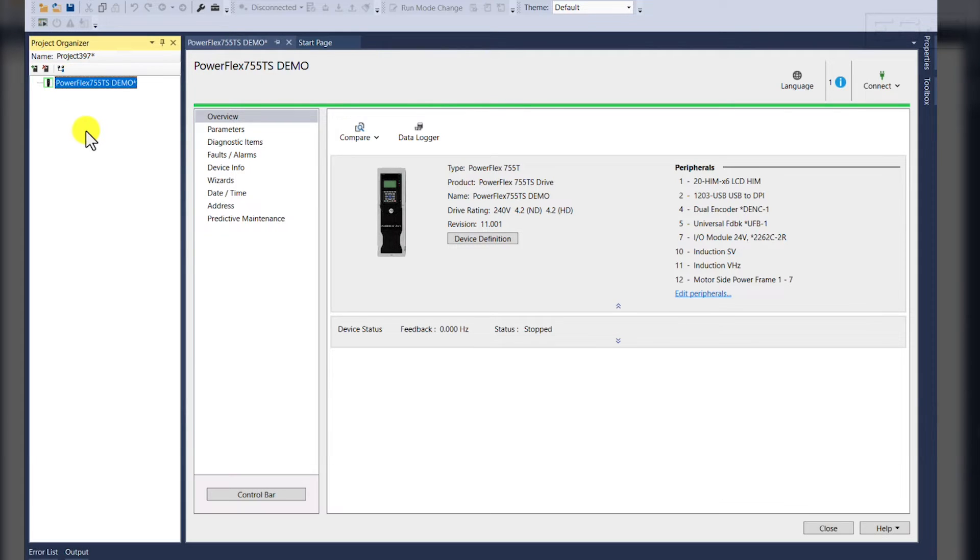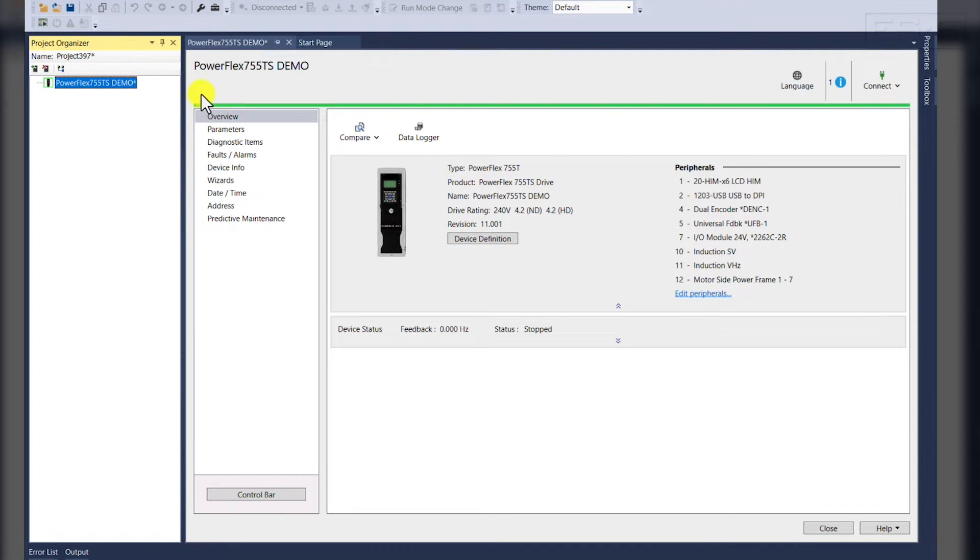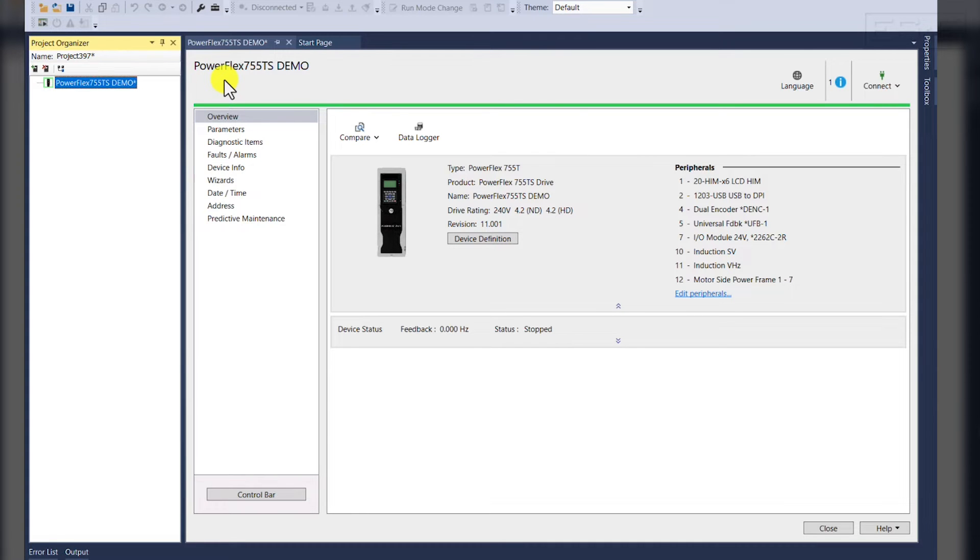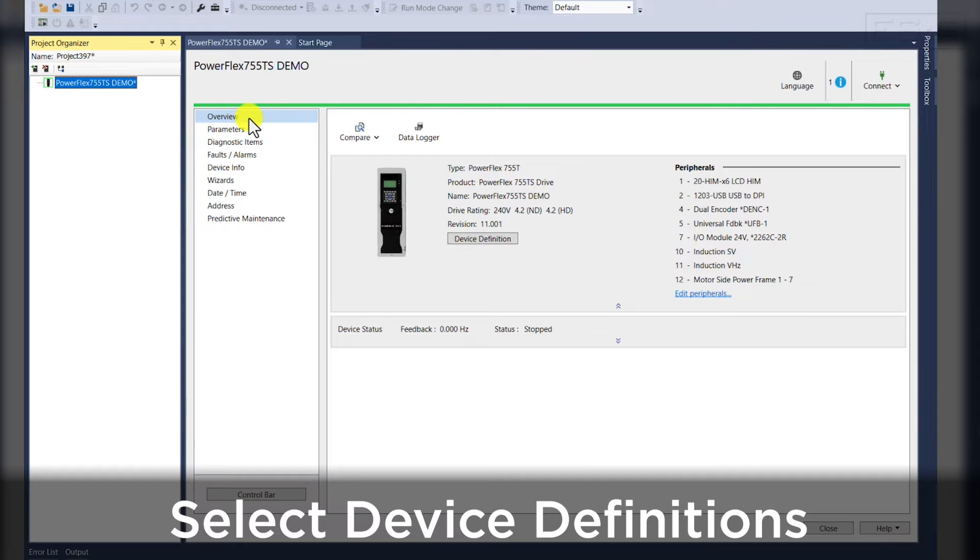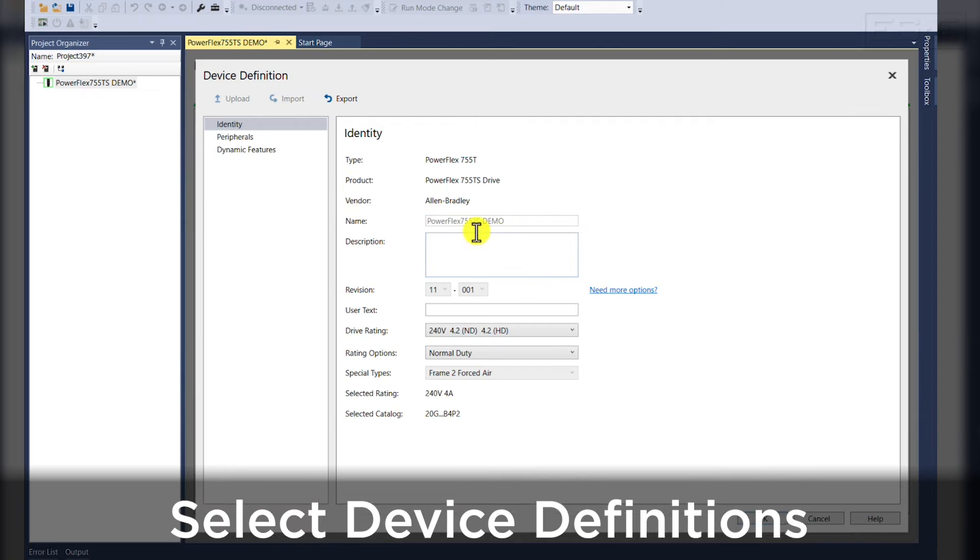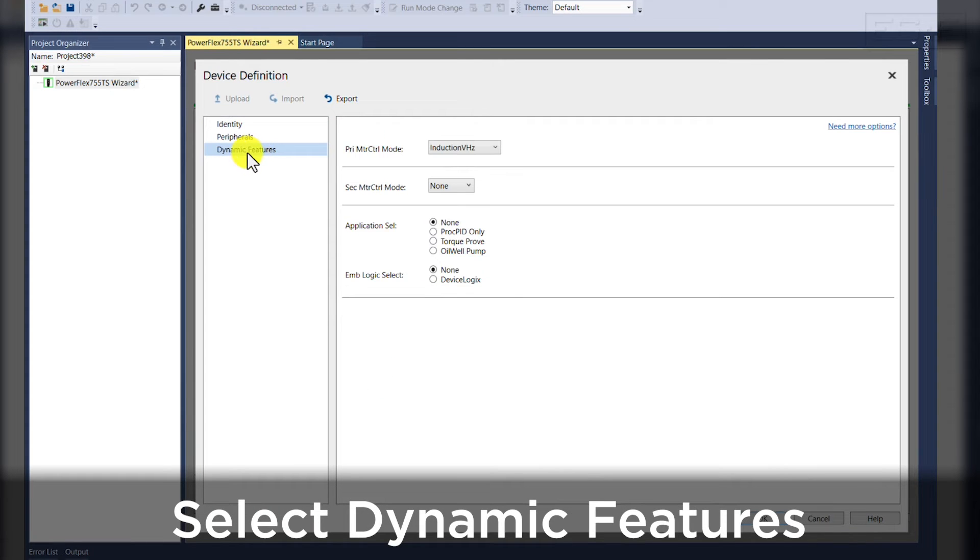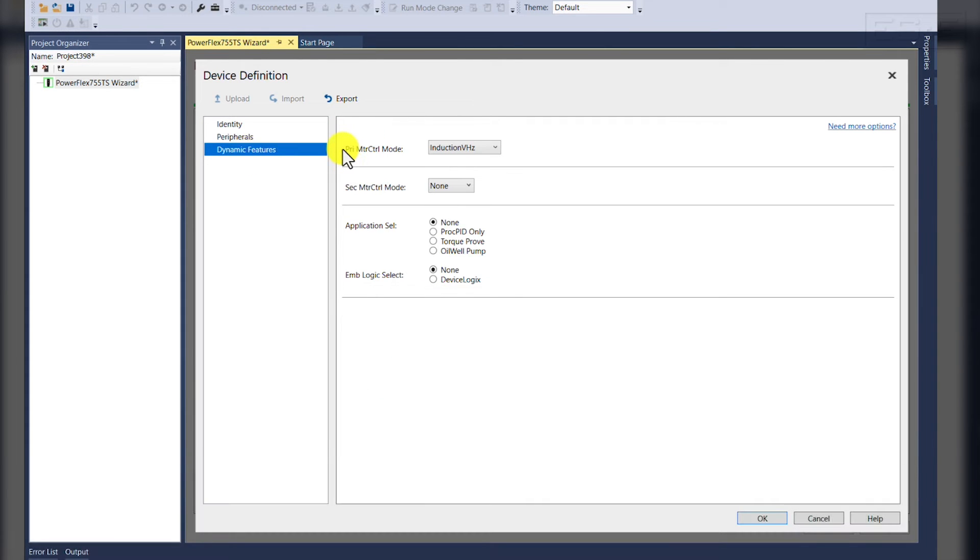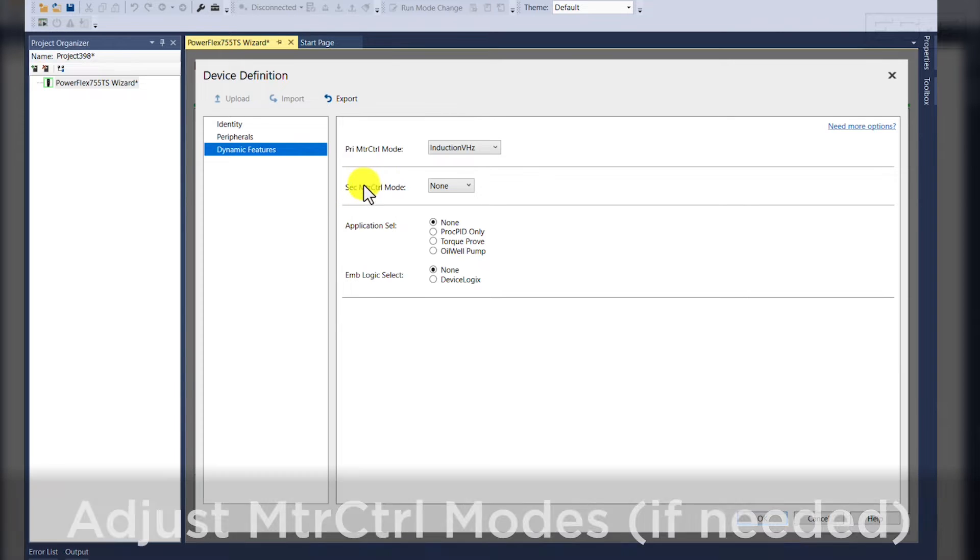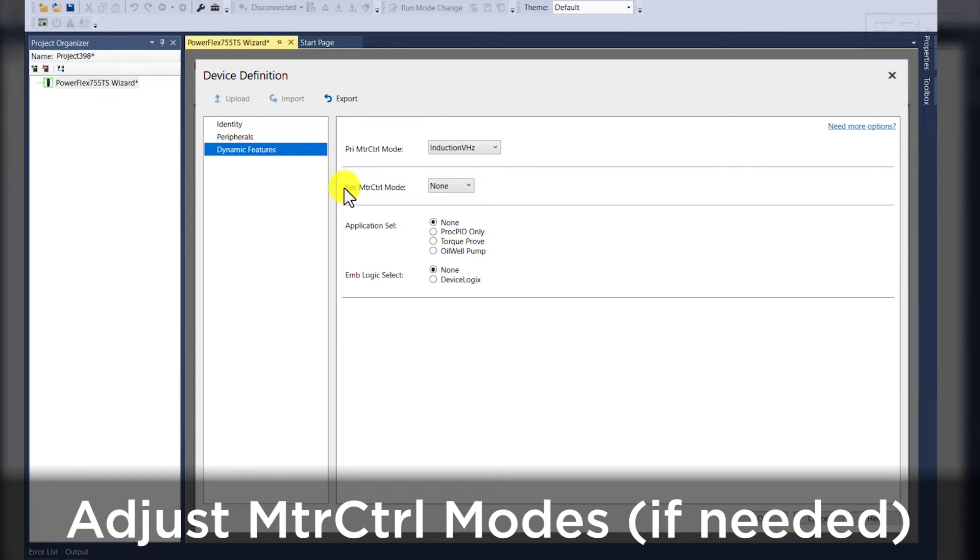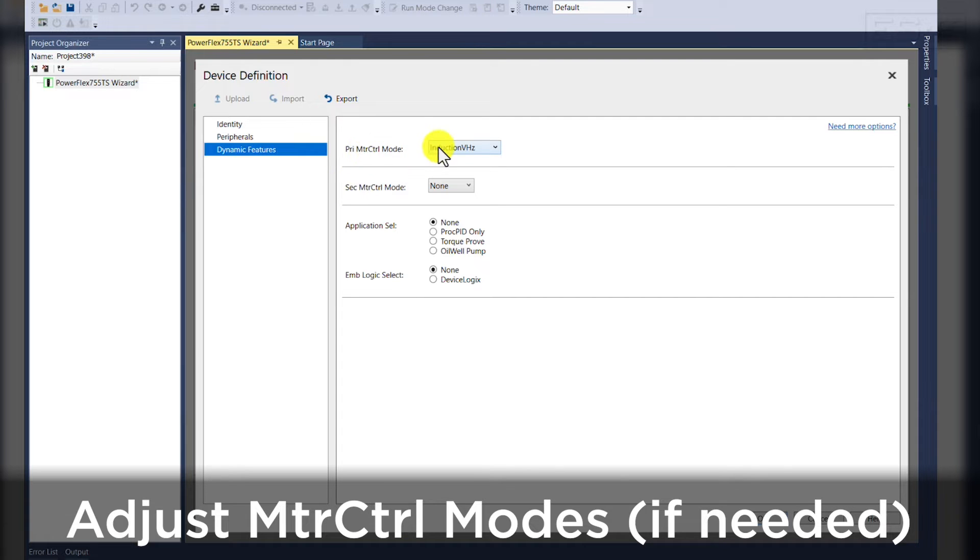Now in a change from the PowerFlex 755, we do want to point out that in order to change motor control methods, there is a different location and a different parameter group altogether. You can access this information on your device's overview tab while clicking Device Definition, Dynamic Features, and you'll see your primary motor control method and your secondary motor control method. In this demonstration, we will disable our secondary motor control method and we will use induction volts per hertz as our primary.